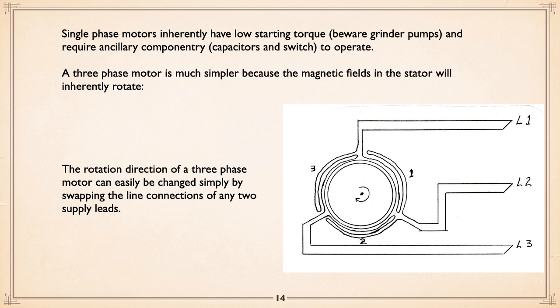Single phase motors we're talking about have very poor starting torque. They really are not good at starting, so watch out. And of course, they require the capacitors and switch. Three-phase motors are simple, and as I mentioned, swap any two leads, and a three-phase motor will go the other direction.